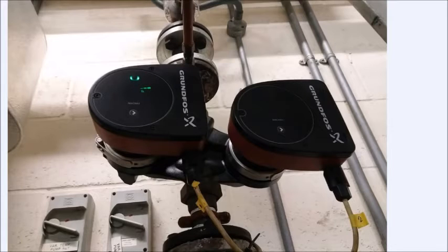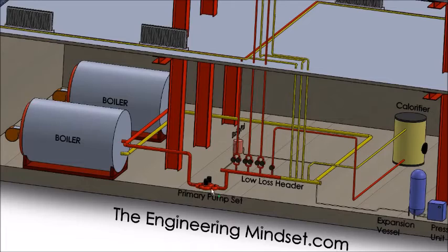So I'll just show you a secondary pump there. So we've got these Grundfos pumps, so these will work to move that water up to wherever it's needed. We'll have a look at that in a second as well. And these will usually work in duty and standby. Same as the primary pumps, they'll also work in duty and standby. And that just means that one of the pumps is on duty, so that's the working pump, and the second pump is waiting for its turn to work.